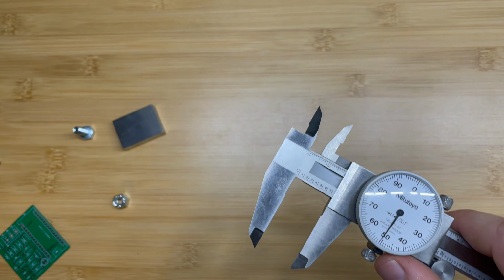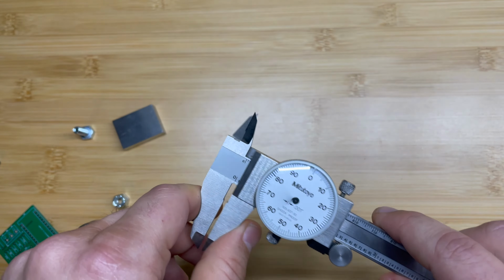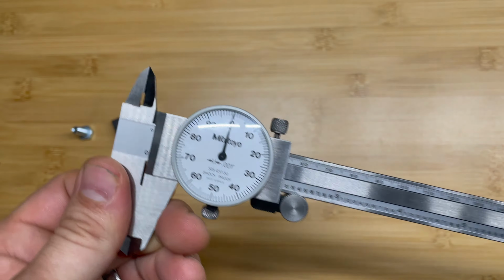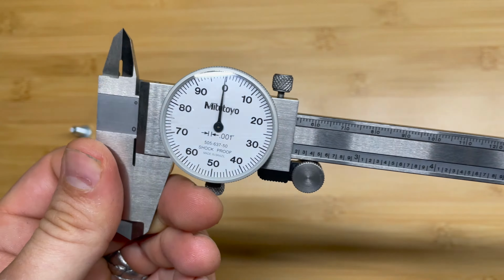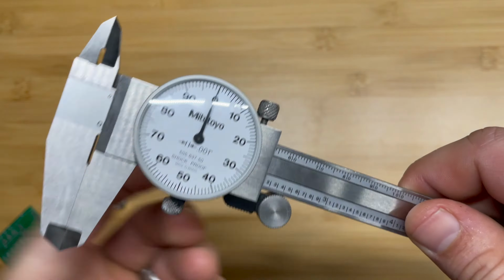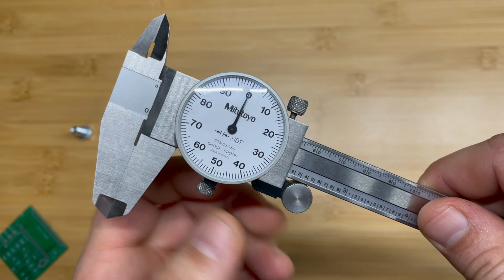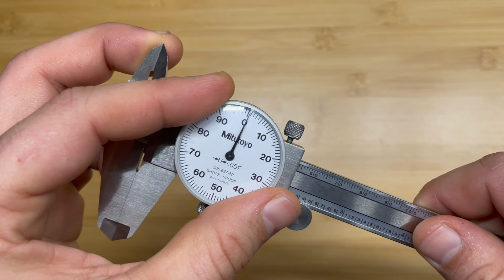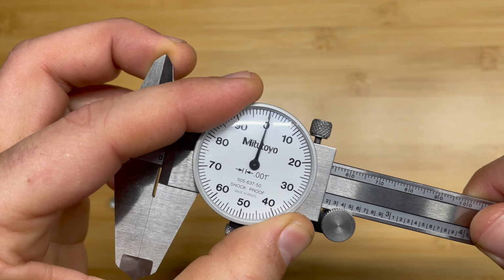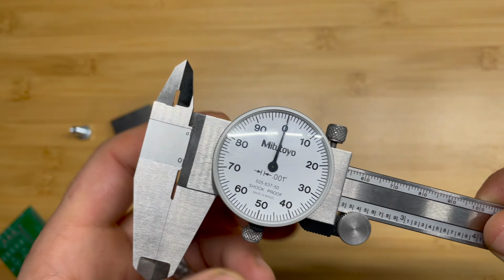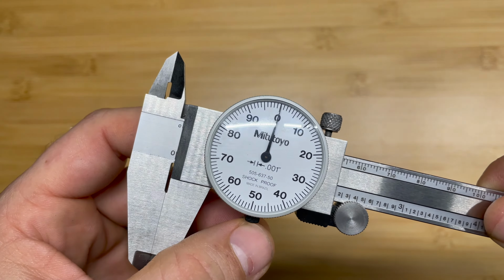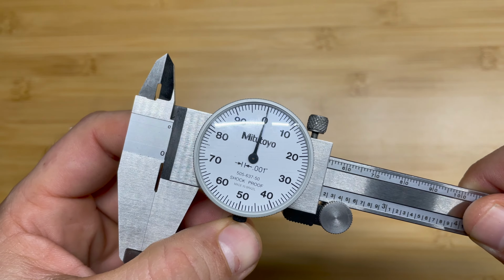You know, we're looking at measuring a thou or 0.001 of an inch. So it's pretty small. It doesn't take much to throw that off. So you want to make sure that's correct. If it's not, you need to loosen this screw down here and you can move the dial accordingly until it's zeroed. Make sure that's zero nice and correct.